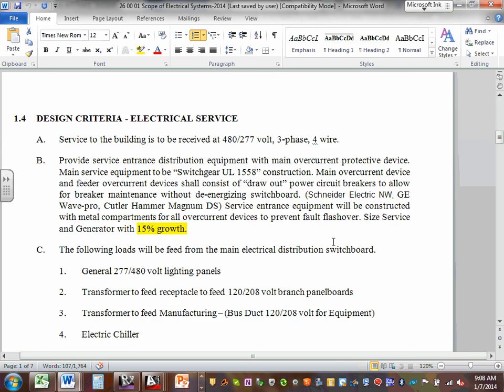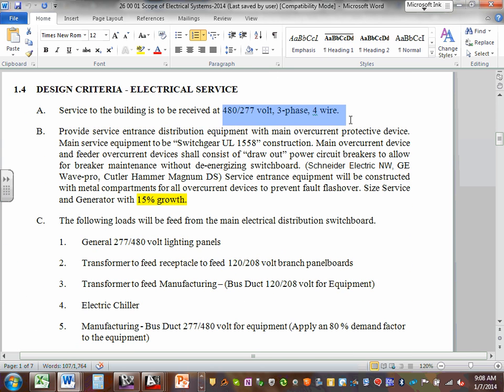The main service is 480 volts coming in. It's going to be UL 1558, which is a little bit of a chunkier piece of switchgear, really well built, usually compartmentalized. The breakers are going to be draw-out circuit breakers, which are the fancy, best of the best type breakers that can quickly and easily get replaced as long as the cradle is still okay. You can pretty much just draw that breaker out and plug a new one in. They're almost plug type breakers. They're pretty cool, but they're really expensive. We talked about some using Schneider Electric, GE, or Cutler Hammer.